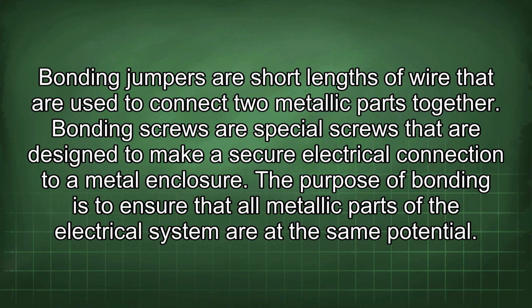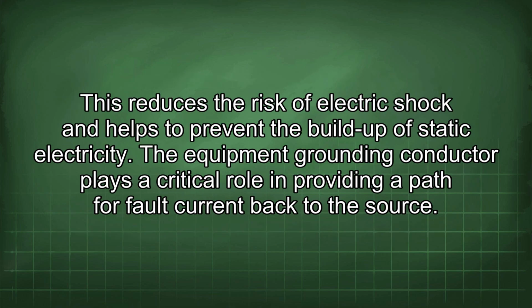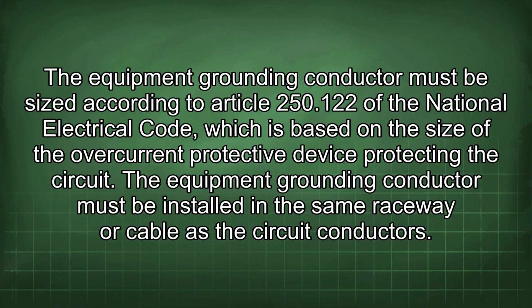The purpose of bonding is to ensure that all metallic parts of the electrical system are at the same potential. This reduces the risk of electric shock and helps to prevent the buildup of static electricity. The equipment grounding conductor plays a critical role in providing a path for fault current back to the source. The equipment grounding conductor must be sized according to Article 250.122 of the National Electrical Code, which is based on the size of the overcurrent protective device protecting the circuit.